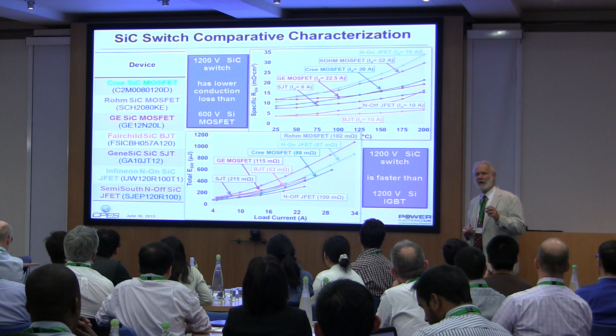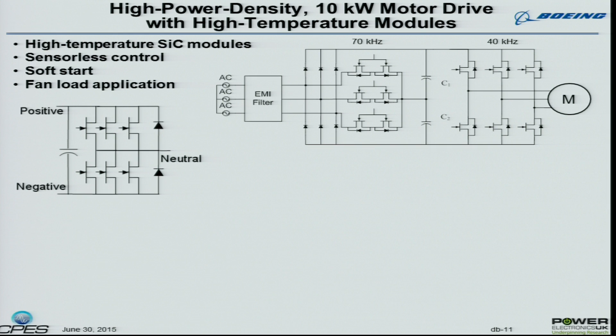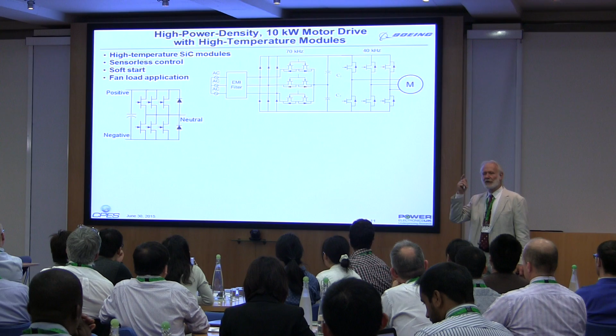We've worked with these for a long time. This was sponsored by Boeing, when we looked at using silicon carbide in a motor drive system with an active front end, inverter, and EMI filter, doing a complete conversion to reduce size. The idea was high temperature modules, not to work in a high temperature environment, but to allow the devices to work at high temperature so the heatsink could be smaller.